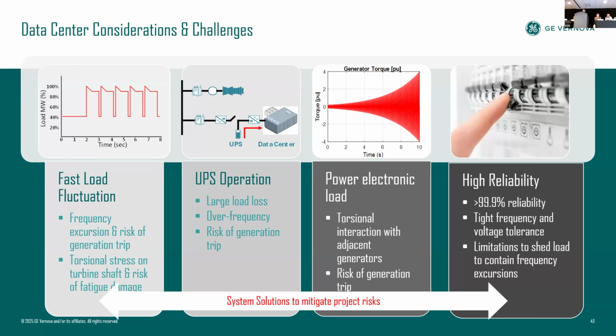On the grid, when we are grid connected, it causes a large drop in power. Now, if the size of the system is big enough, that power is absorbed by the grid. That's why we don't see these issues yet, although there are some reports from NREL regarding the issue that was shown in the Maryland area, right? So this non-fault ride-through characteristic of the load, together with the UPS tripping based on frequency and voltage thresholds, causes a big problem when we're talking about the islanded power system.